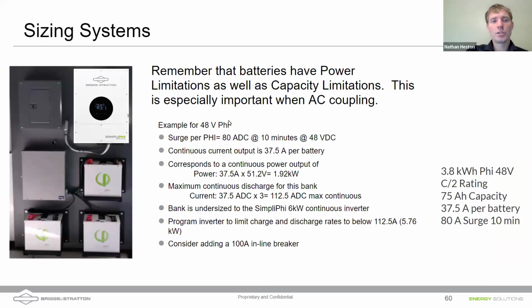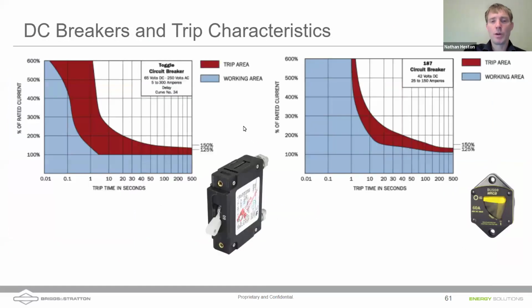I do want you to consider sizing your equipment properly. Remember that when you're using operating equipment, the batteries themselves have power limitations, so you'll want to make sure to program the rates appropriately into your equipment. Also, DC breakers have trip times, and it's important to consider those when using them to protect batteries and cabling.